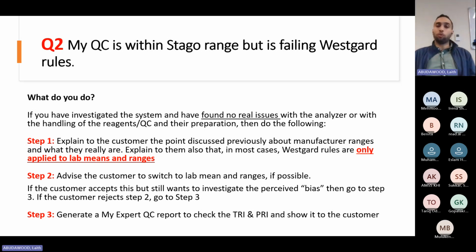Very important point with Westgard rules. Applying them to manufacturer ranges in most cases is wrong. Westgard rules are not made to be used with manufacturer ranges. We don't have the time to get into the very deep details for why that is. But they generally perform very, very poorly with manufacturer ranges. It's not the fault of Westgard rules, it's the fault of applying Westgard rules where they should not be applied.